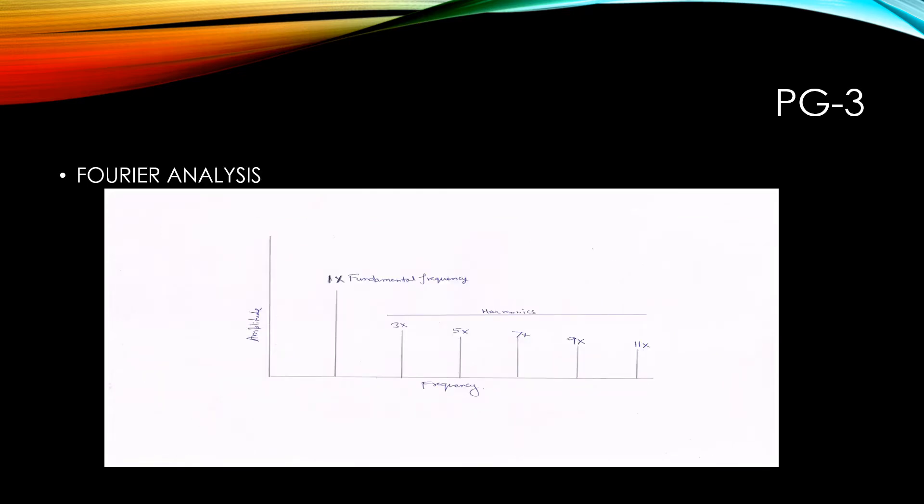Let us discuss the most important part of this topic, Fourier analysis or we call it spectrum analysis also. This would help us to know which part of the machinery is troublesome. Fourier analysis is the term for the transformation of a time waveform into a spectrum of amplitude versus frequency values. It is also known as spectrum analysis and it can be done with a fast Fourier transform analyzer.